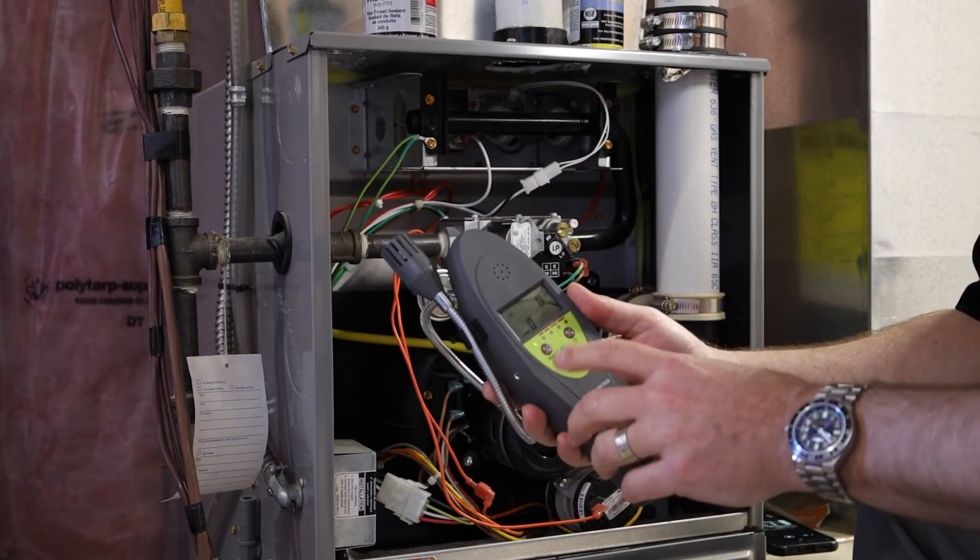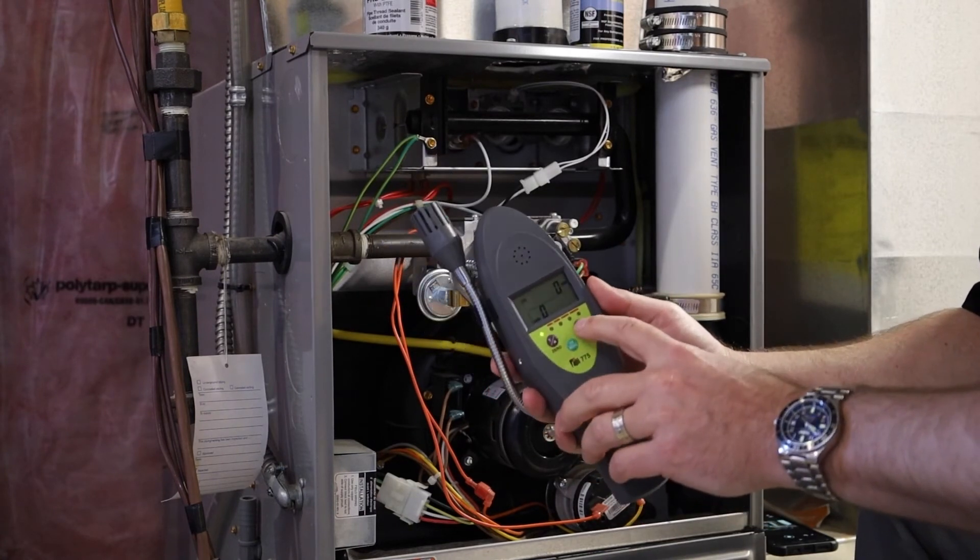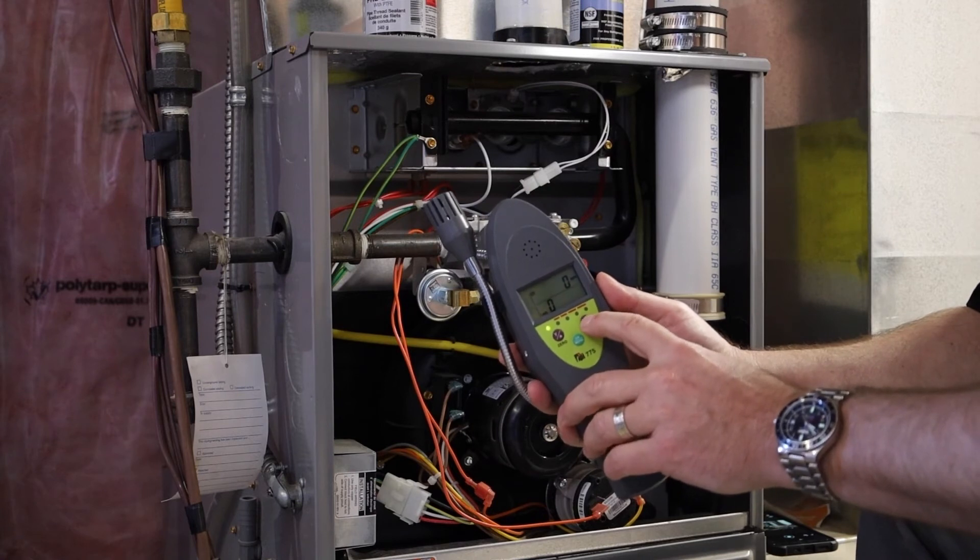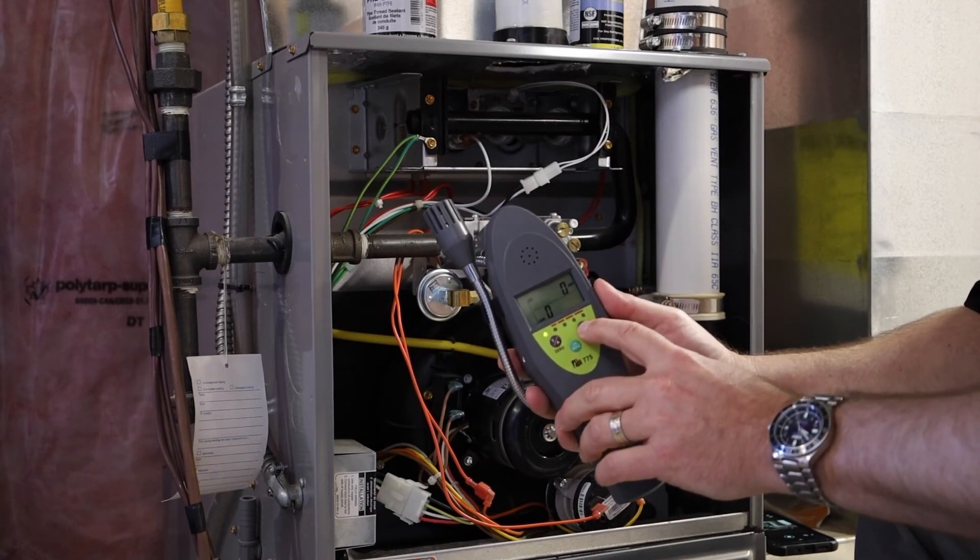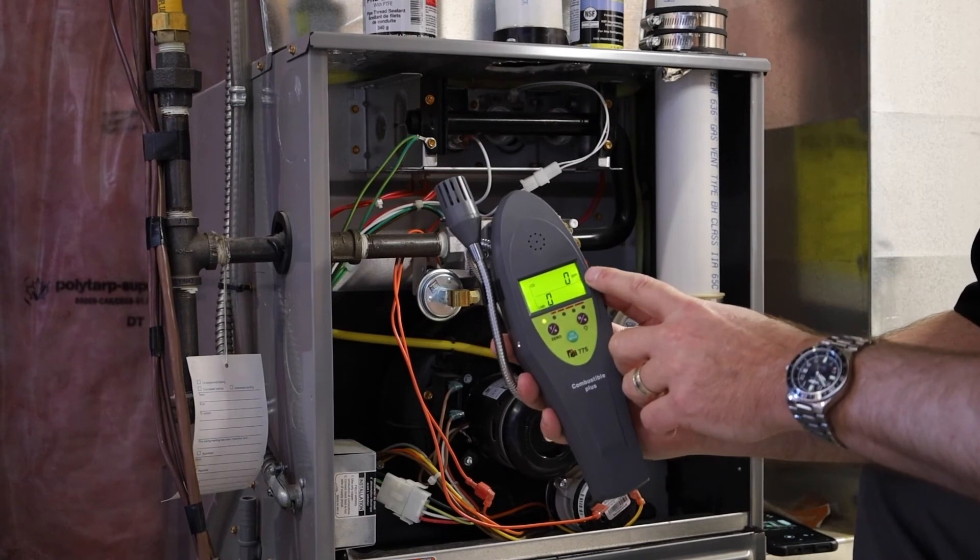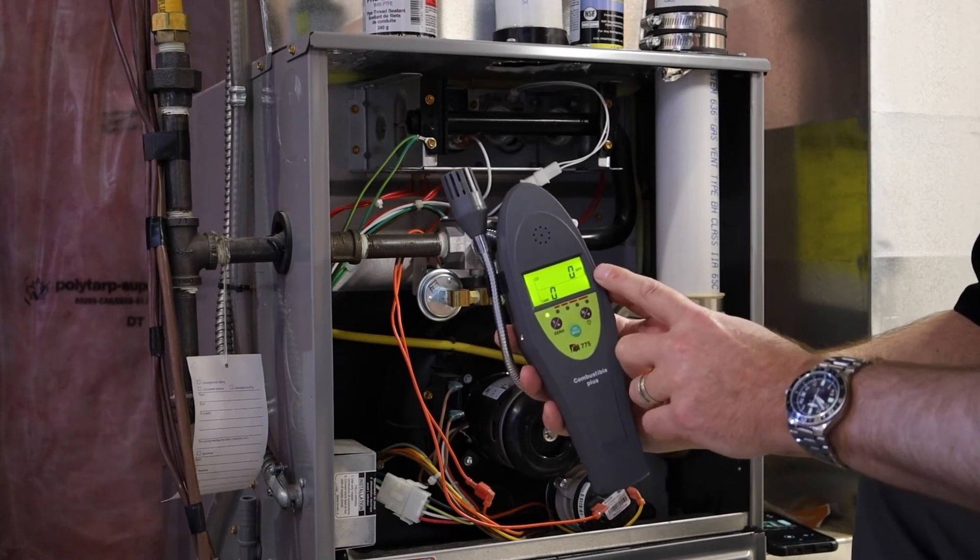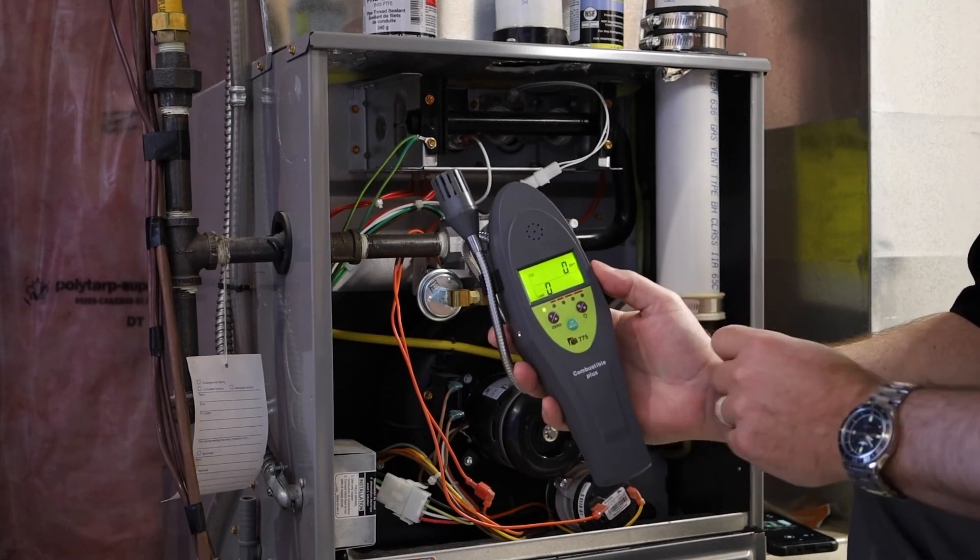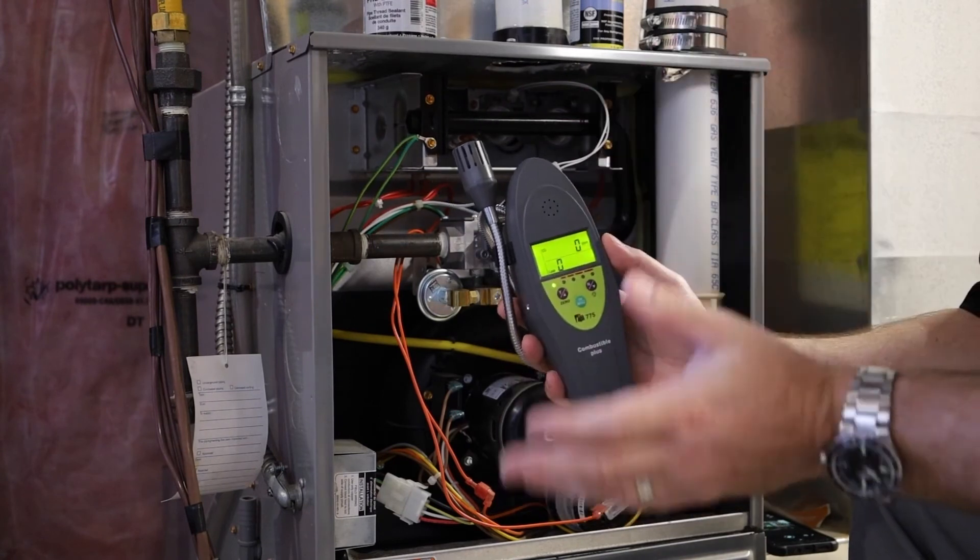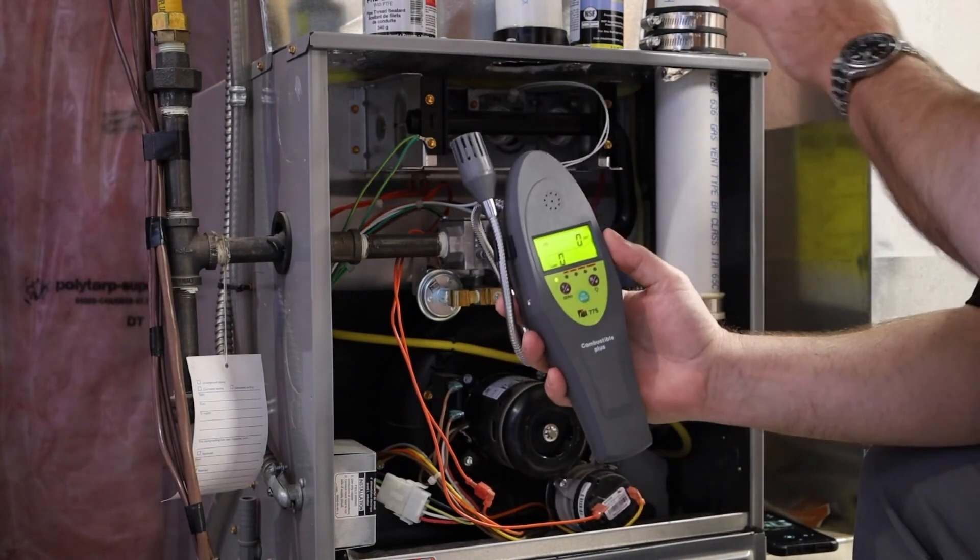So again, this one is giving us an LCD display. And I'm just going to turn on the backlight, make sure you can see that good. And it shows right here, CO in parts per million. So this will actually measure up to 2,000 parts per million. Again, this is just for indoor air quality. It's not for inside the flue of the appliance.